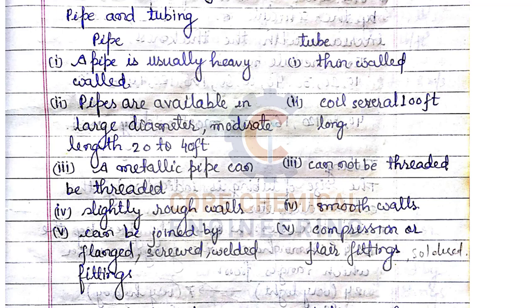In any industry, most processed fluids, utilities, or steam travel through pipes. Tubes, by contrast, have a very small diameter and are used for instrument air supply in the control room or for steam tracing around pipelines for heat conservation. A pipe is usually heavy-walled and available in large diameters with a moderate length of 20 to 40 feet.